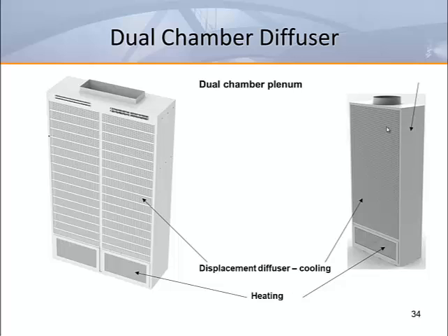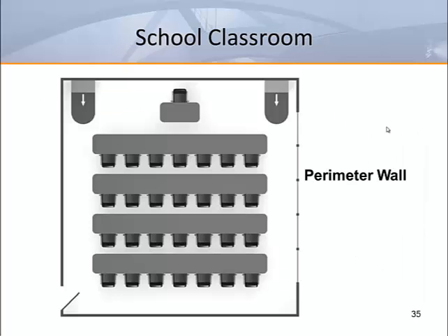The diffuser shown on the left uses onboard technology to switch the baffle from cooling to heating position based on the temperature of the supply air. The diffuser on the right directs the air to the proper chamber based on the thermostat setting for either heating or cooling. In a classroom, this is a floor plan diagram that shows how a classroom may be set up for displacement ventilation comfort control. Two diffusers at each corner of the front of the classroom will comfort condition half of the room.